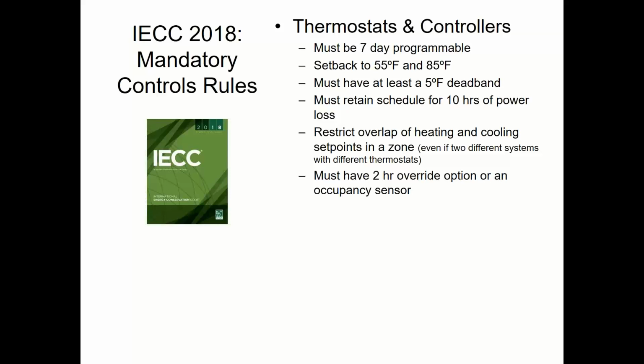If you didn't know, for energy code compliance, you have to use programmable stats. It's not even an option. You have to use programmable stats. They have to be 7-day programmable. Those 5+2s don't count. By the way, a 5+2 is a residential stat. No one's ever made a commercial thermostat that was 5+2. All the commercial ones are always 2-stage. They're always 7-day programmable. Anything else is a residential stat being put into a commercial building.